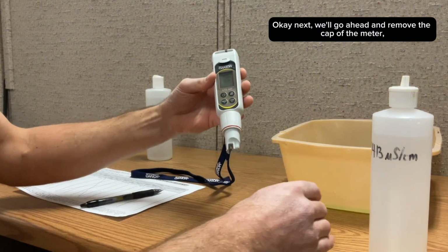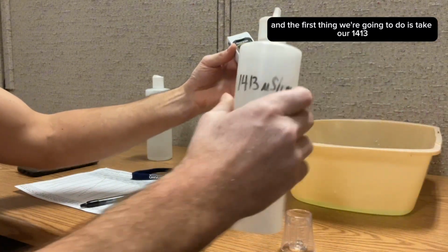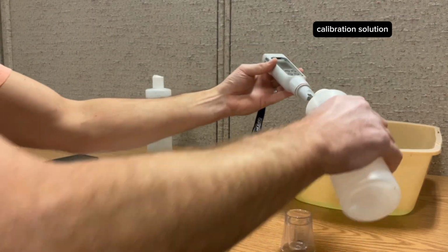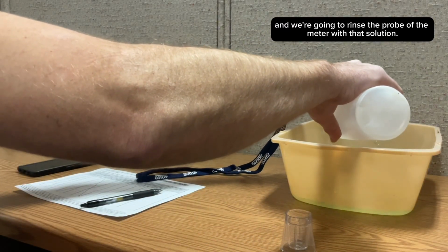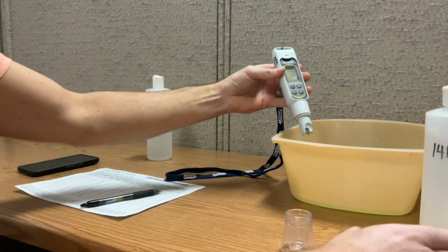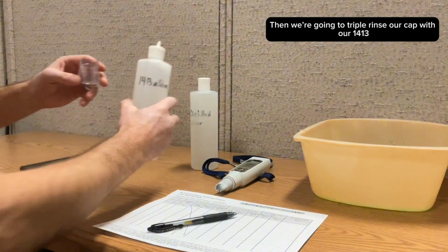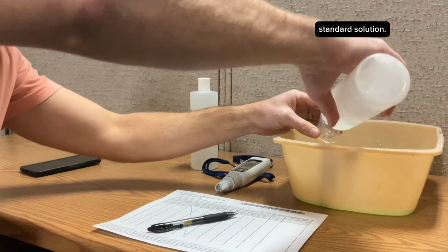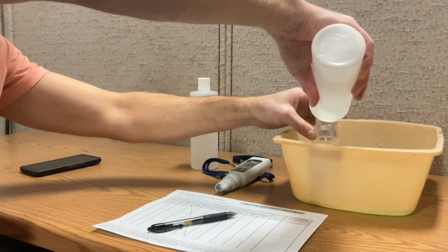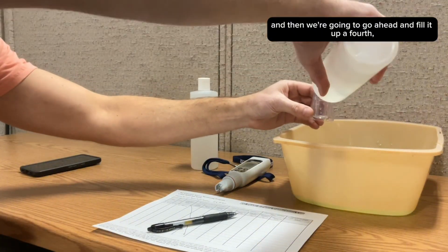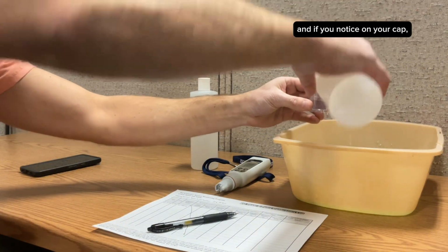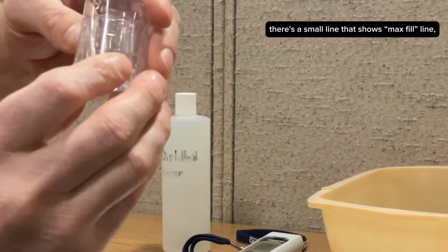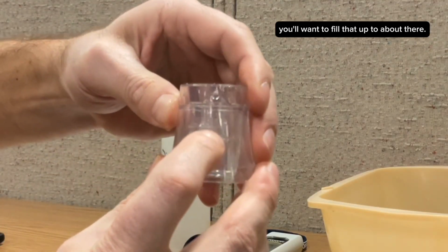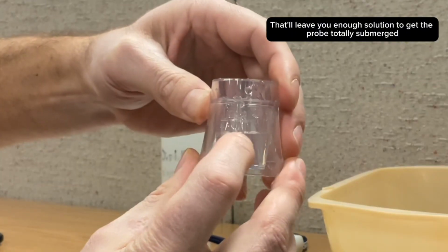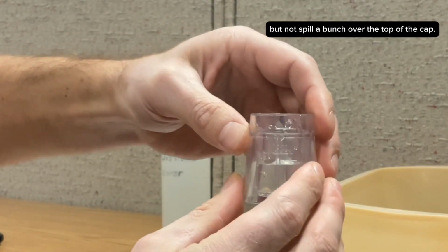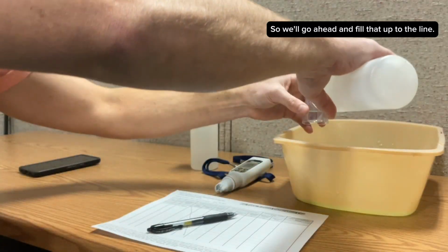Okay, next we'll go ahead and remove the cap of the meter. And the first thing we're going to do is take our 1413 calibration solution and rinse the probe of the meter with that solution. And we are going to triple rinse our cap with our 1413 standard solution. Rinse it out 3 times, dump it out a third, and then we're going to go ahead and fill it up a fourth. If you notice on your cap, there's a small line that shows max fill line. You'll want to fill that up to about there. That'll leave you enough solution to get the probe totally submerged, but not spill a bunch over the top of the cap. So we'll go ahead and fill that up to the line.